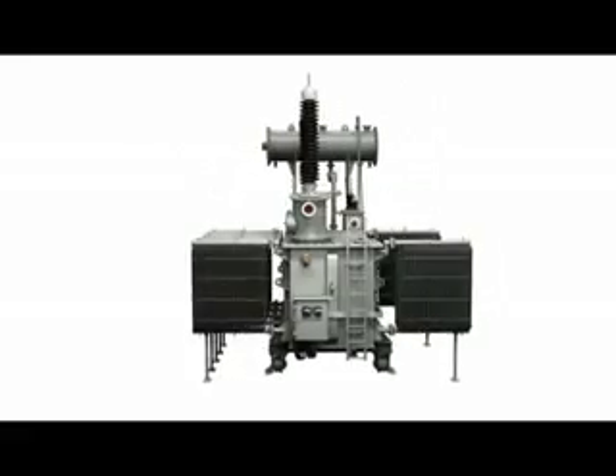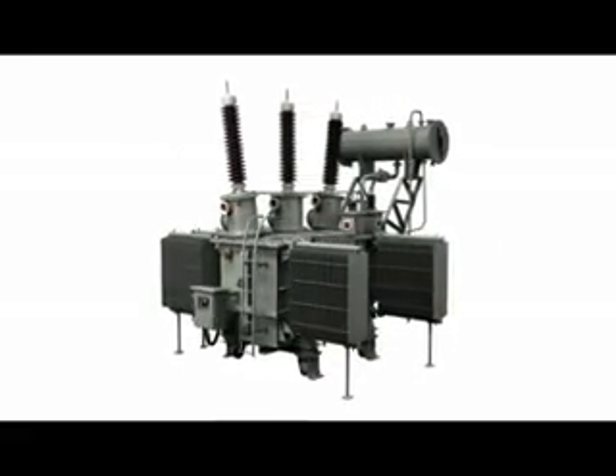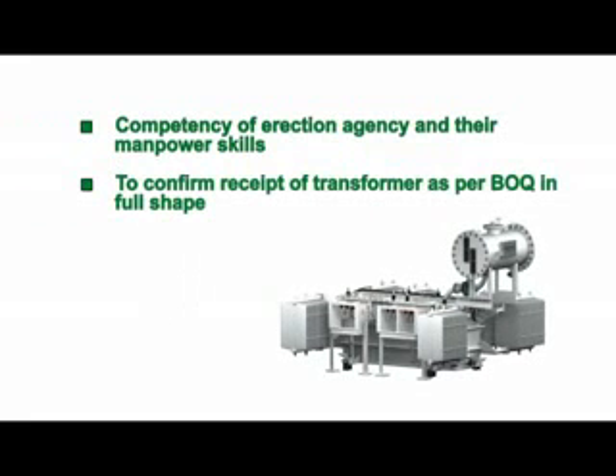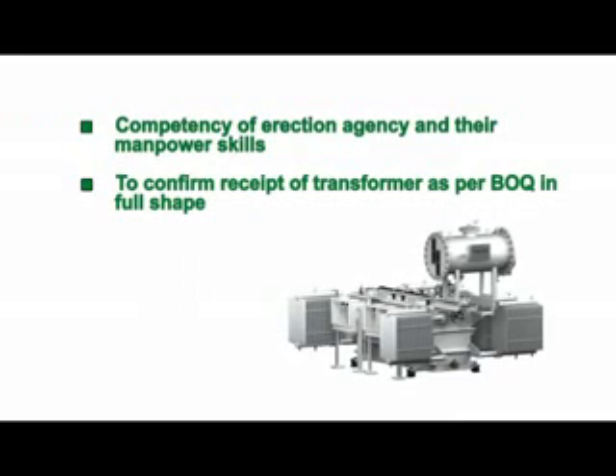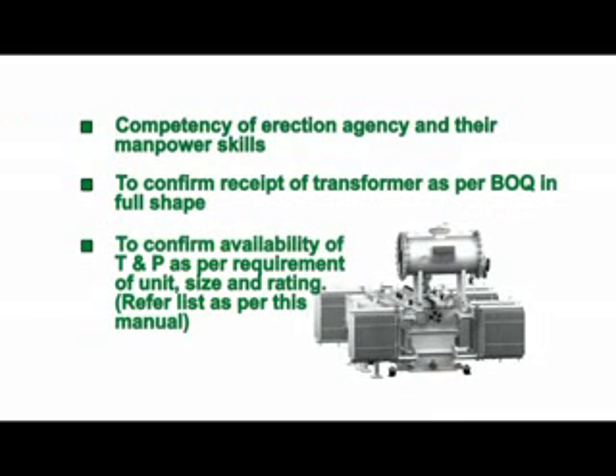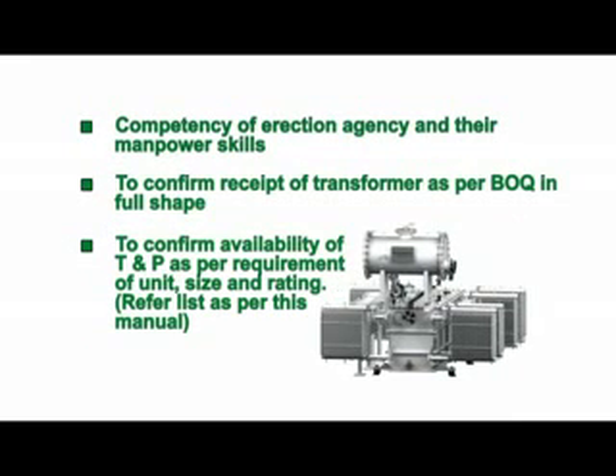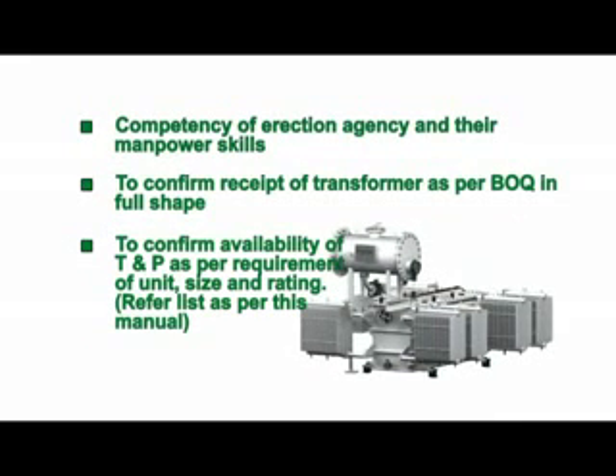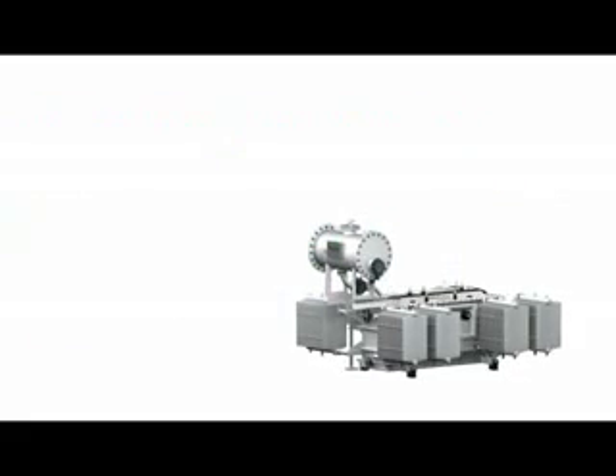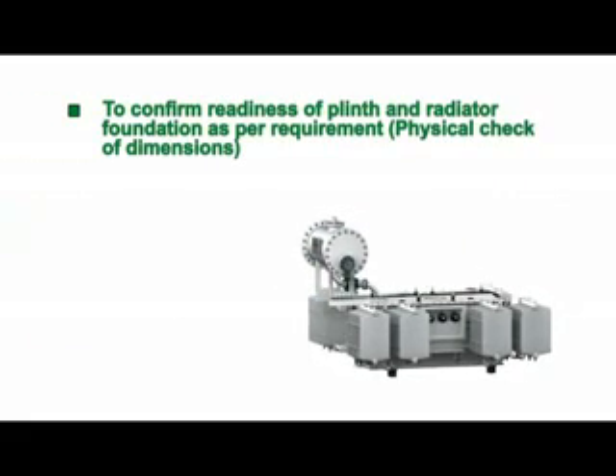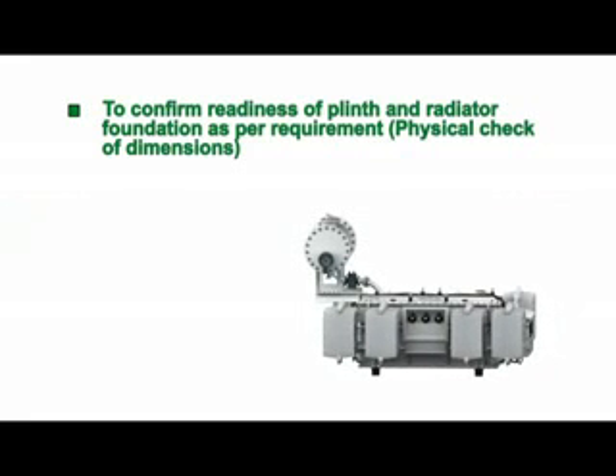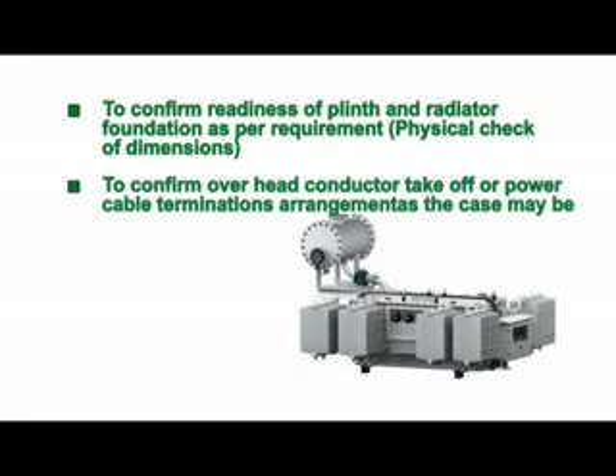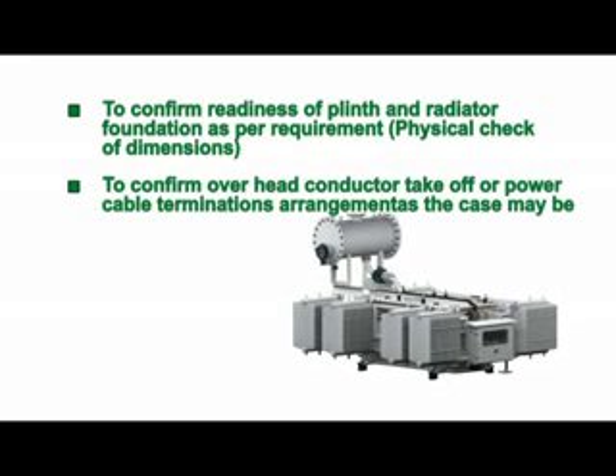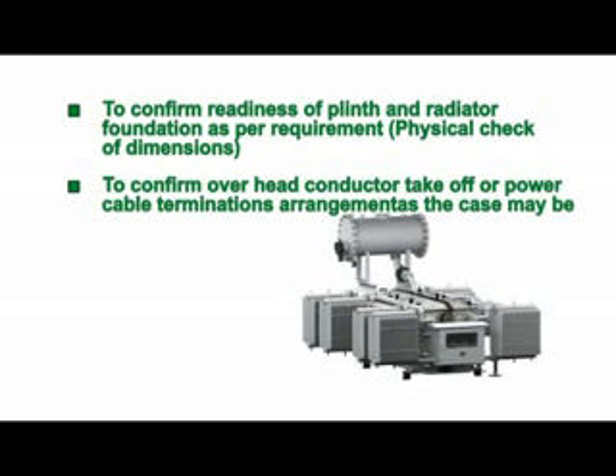transformer parts or items. It is suggested to have a kick-off meeting, KOM, with the following main agenda: competency of the erection agency and their manpower skills; to confirm receipt of the transformer as per BOQ in full shape; to confirm availability of T&P as per requirement of unit size and rating. Refer to the list in this manual. To confirm readiness of plinth and radiator foundation as per requirement. Physical check of dimensions. To confirm overhead conductor takeoff or power cable terminations arrangement as the case may be.